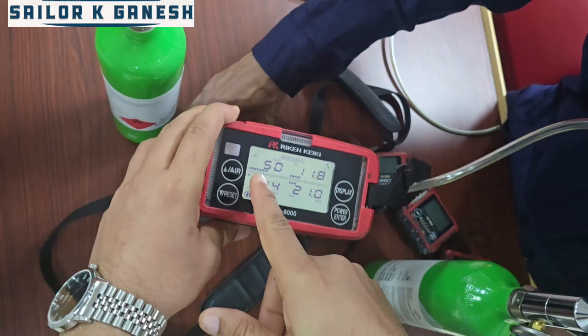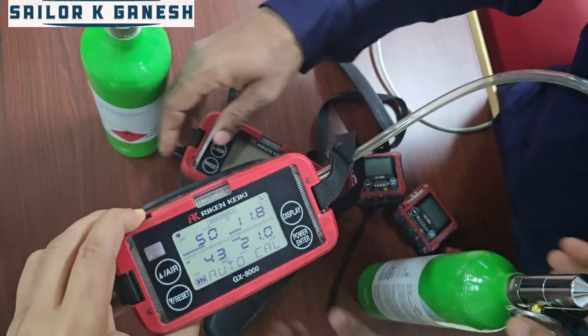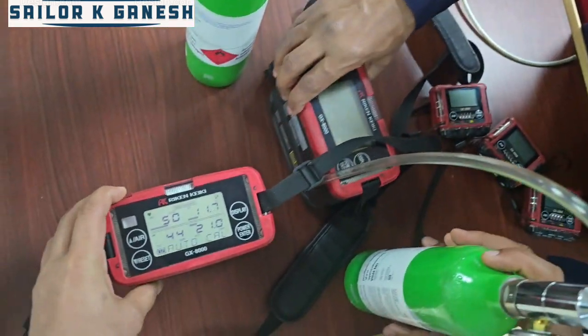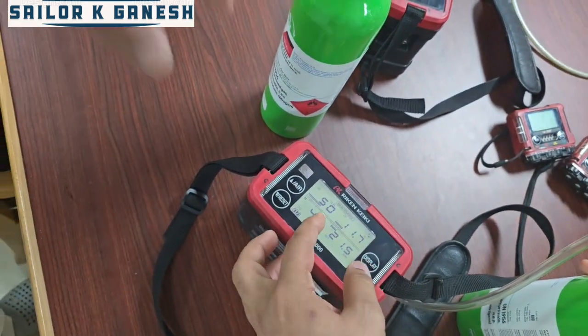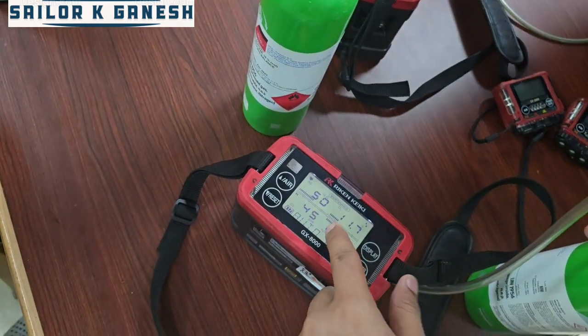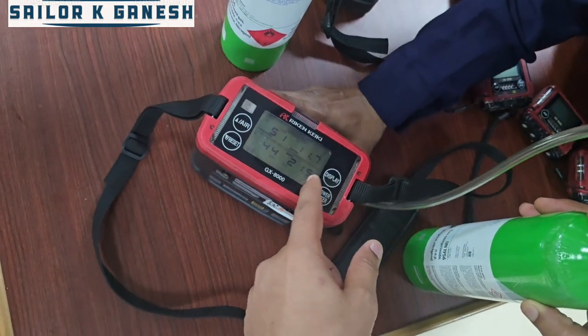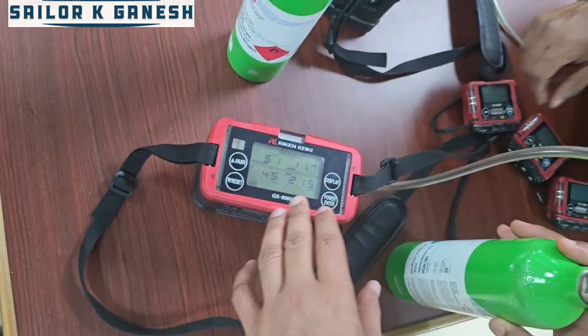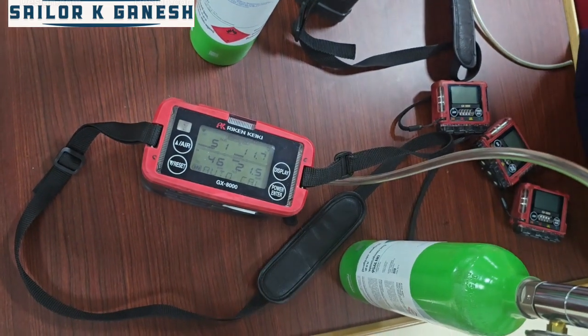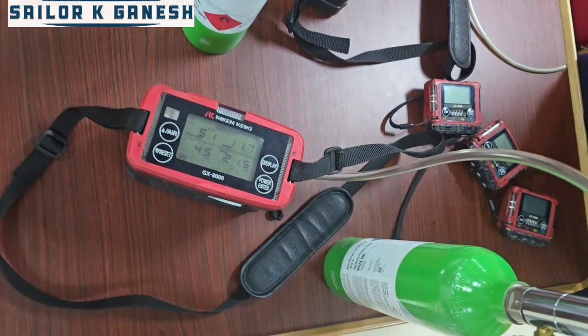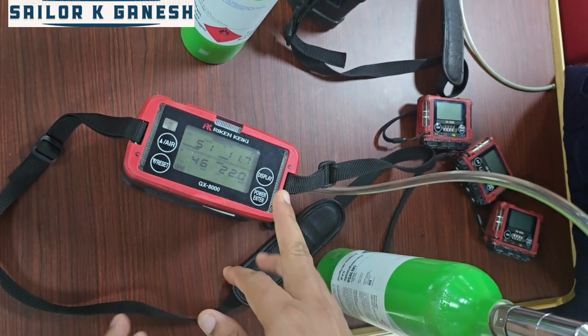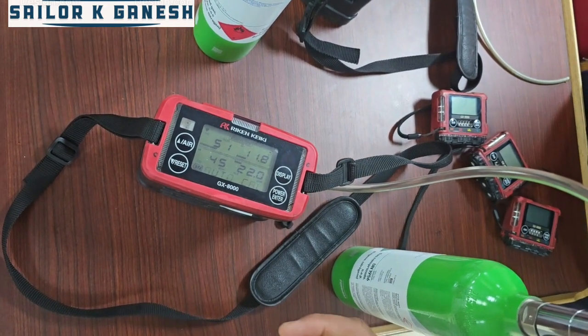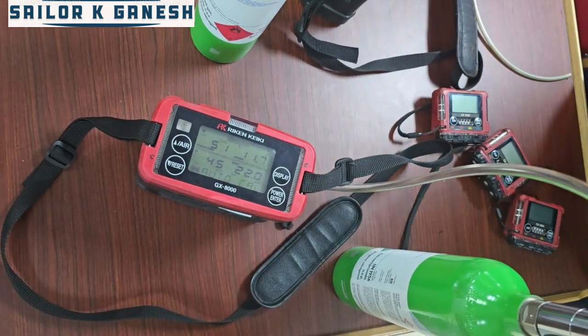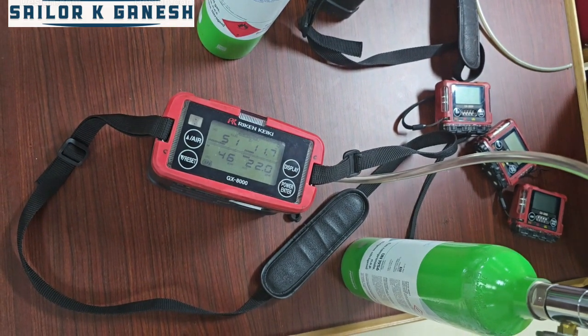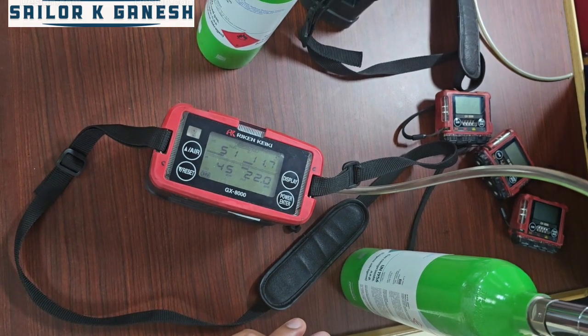So now you can see that the hydrocarbon 50%, which is inside this bottle, is showing correct. Oxygen 12%, this is almost close to 12%, and the CO 50 is almost close, 45. And the H2S 20 is 21.5. So slowly it will calibrate automatically. Once you reach the set values, you can press the enter key, and it will automatically do the calibration of the equipment, and you will get to know whether it is pass or fail.